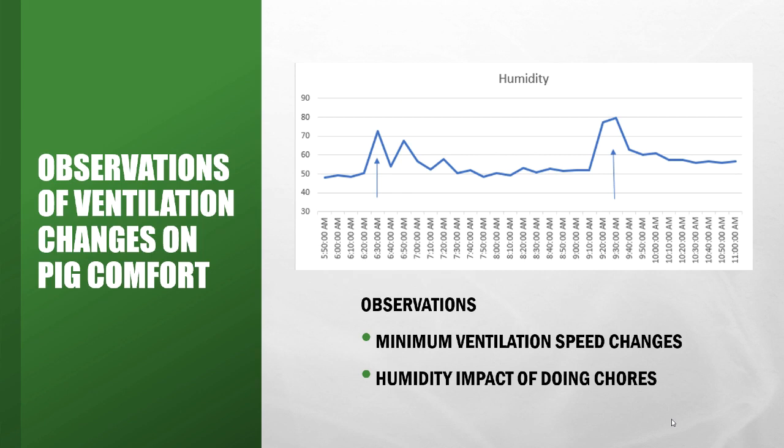Let's face it, with turnover, a lot of our team members aren't ventilation experts. So we're really trying to zero in on this and understand what we're trying to get done with the air. Especially early, when you're keeping nurseries at 86, 87 degrees, starting them out, we've got to get enough air in there to grab the moisture and get it out the fan. And so making adjustments based off humidity is not a big one in our system anymore. It's more off the lying patterns.